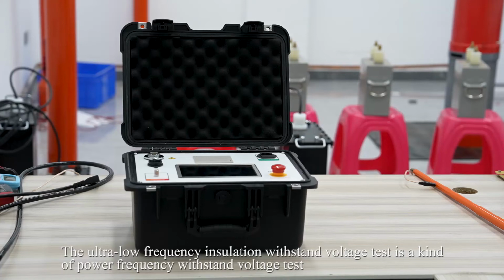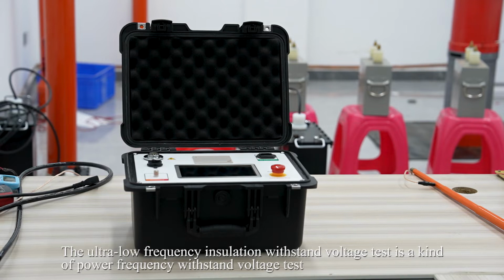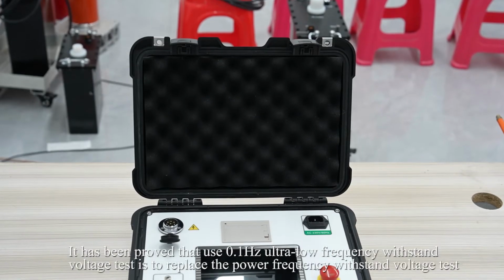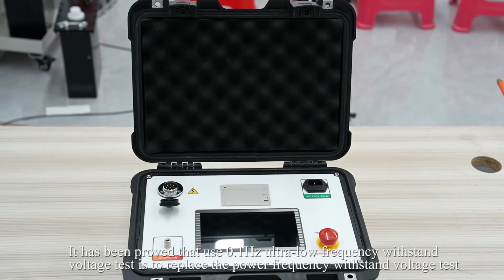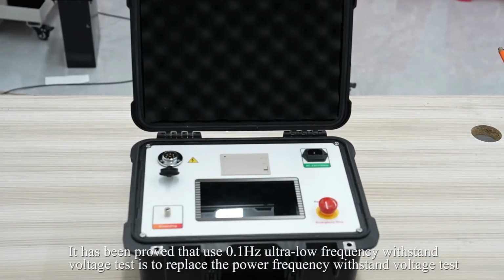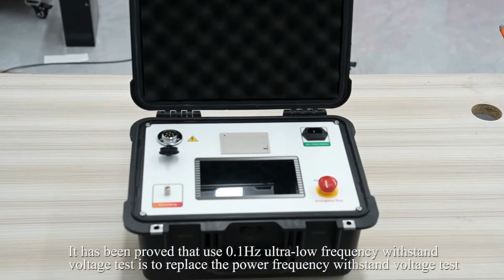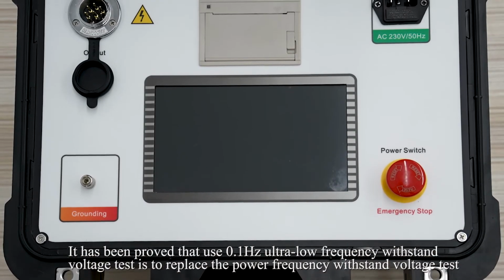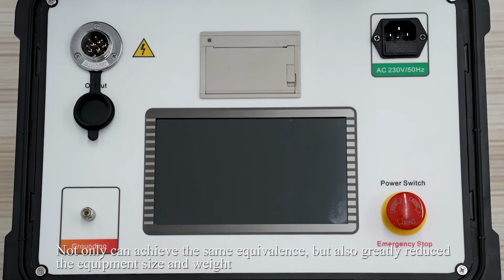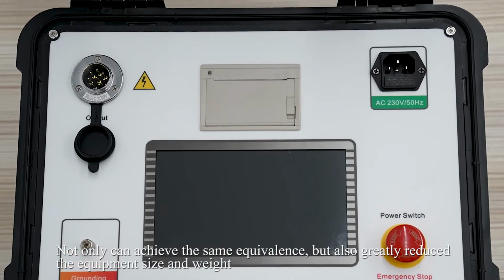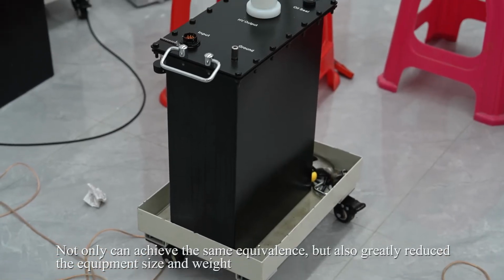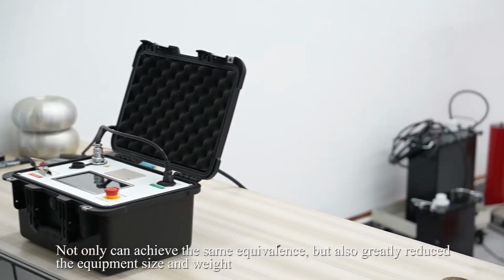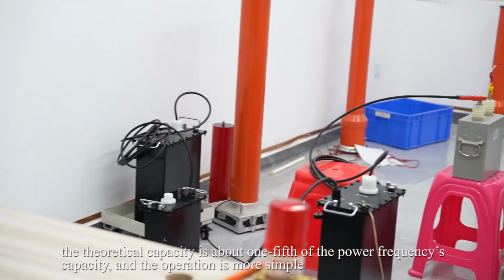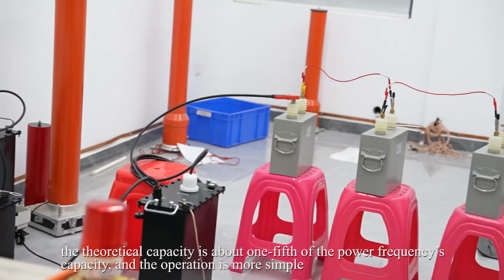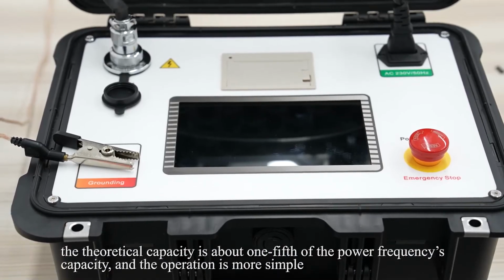The ultra-low frequency insulation withstand voltage test is a kind of power frequency withstand voltage test. It has been proved that using the 0.1 Hz ultra-low frequency withstand voltage test to replace the power frequency withstand voltage test can not only achieve the same equivalence, but also greatly reduce the equipment size and weight. The theoretical capacity is about 1/5 of the power frequency capacity, and the operation is simpler.